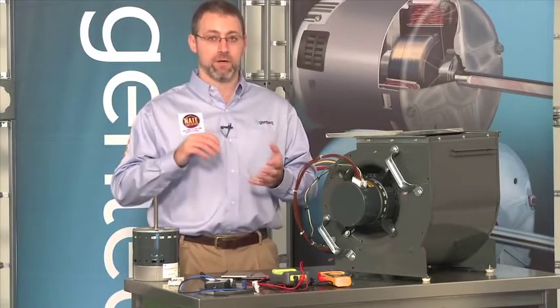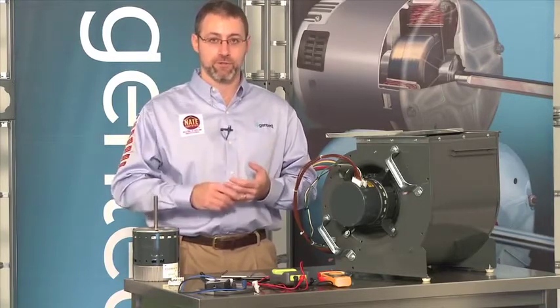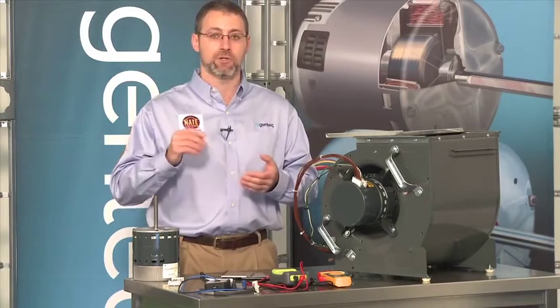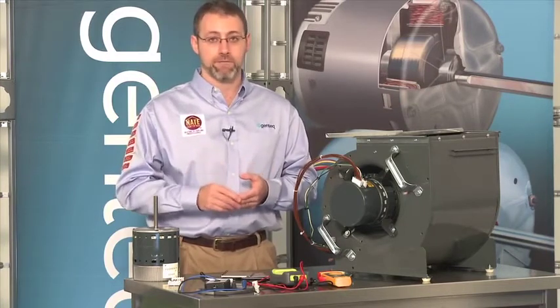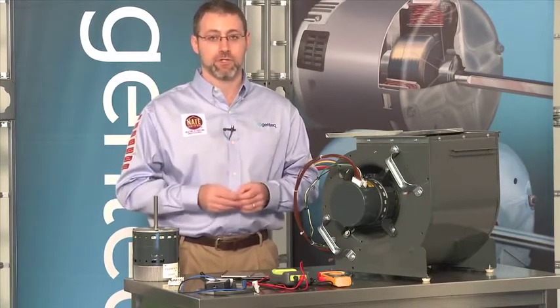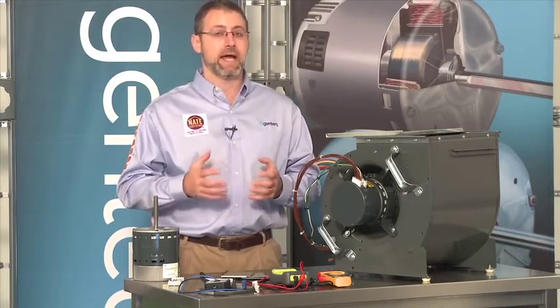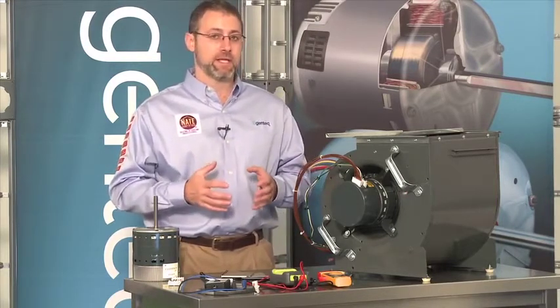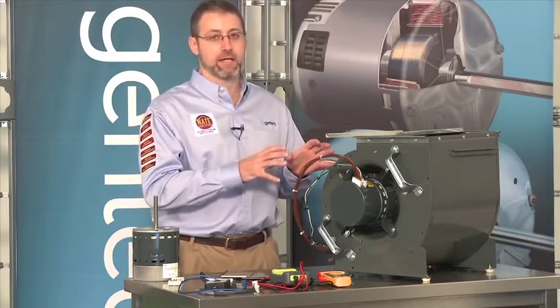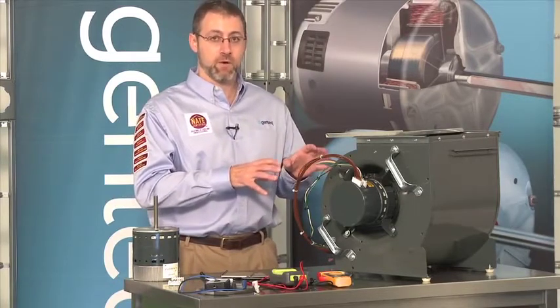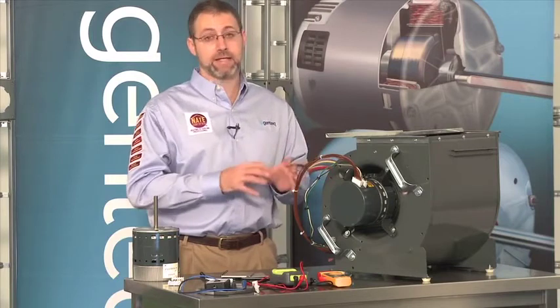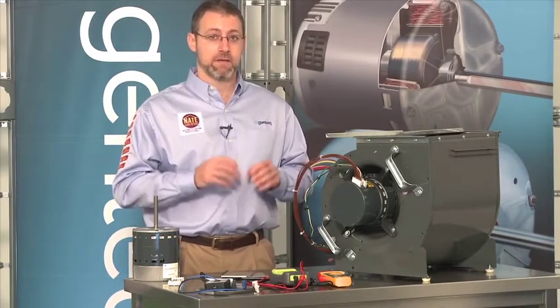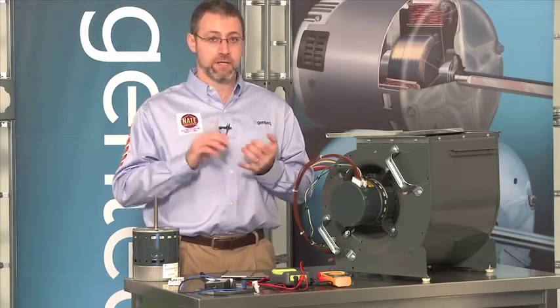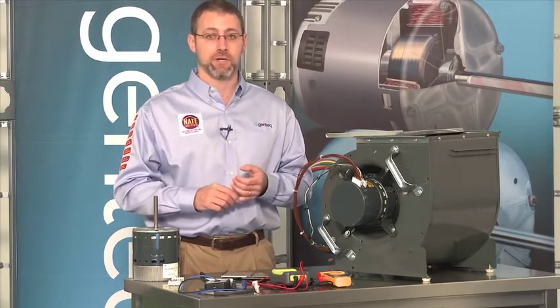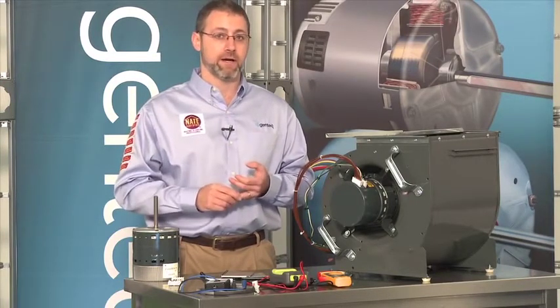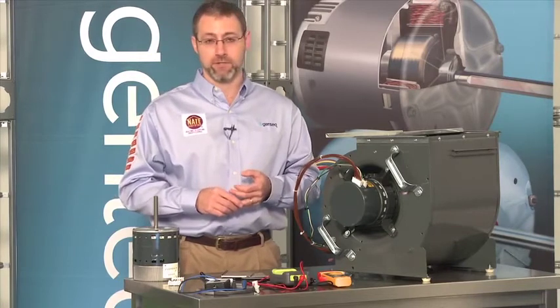That means if your ductwork is too small, your filters are too dirty, your registers are closed, or even if you don't have the right airflow selected from the dip switches or jumper pins on the boards, you might not have the right airflow. So what I'm getting at is there's going to be times where you're diagnosing a variable speed system where the motor's running, but you're not necessarily getting the airflow you need. In that case, I would go after the dip switch and jumper pin settings using the OEM manual, and I would check all of my airflow concerns on my system.